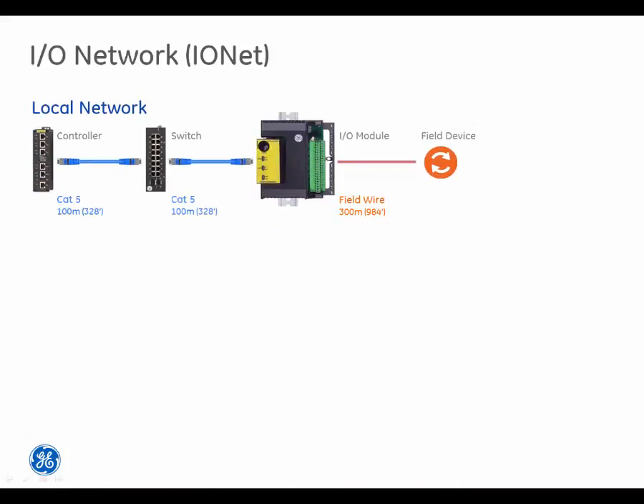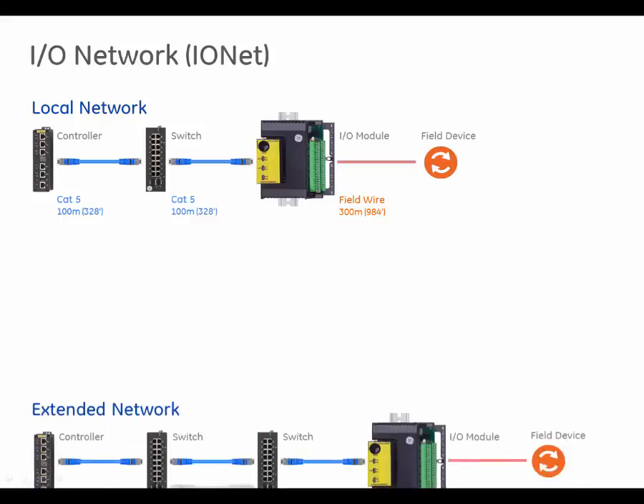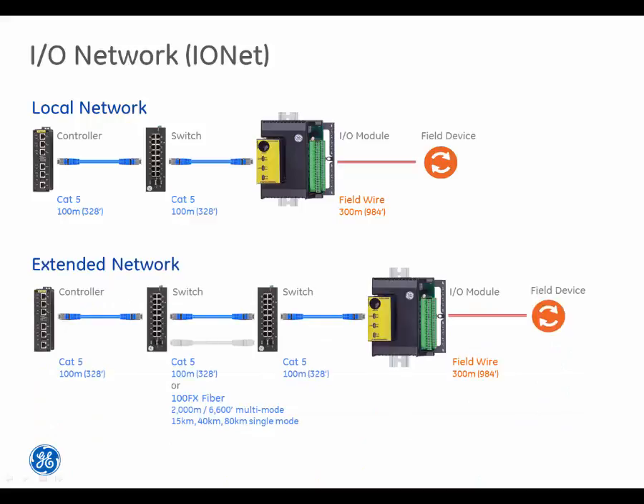The I/O network, or I/O net, utilizes a dedicated full duplex point-to-point protocol. It supports a deterministic 100 megabit communications network suitable for local and distributed I/O modules. In each communication frame, the online controllers read data from the input modules, write data to the output modules, and synchronize variables between controllers in a dual or TMR configuration.